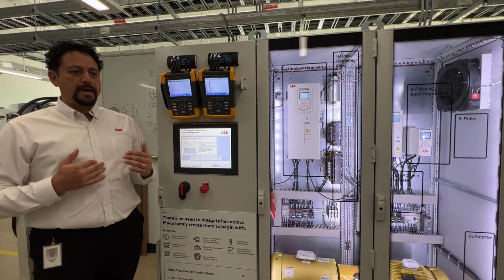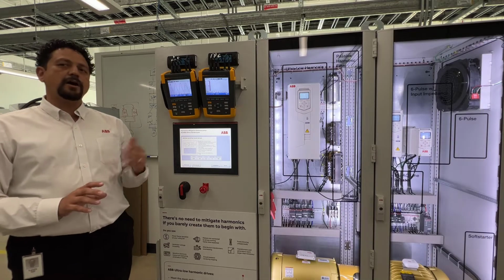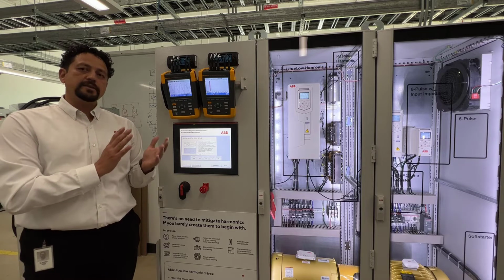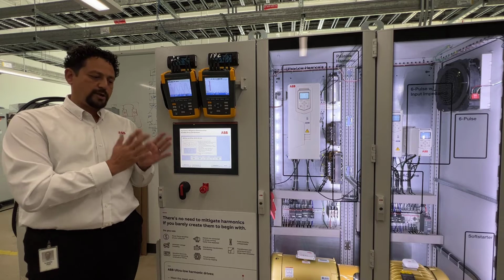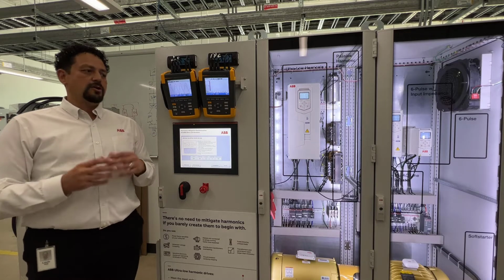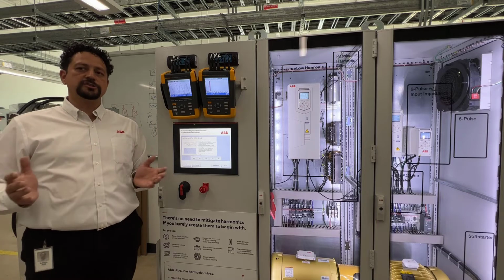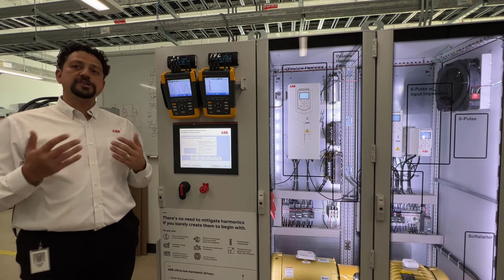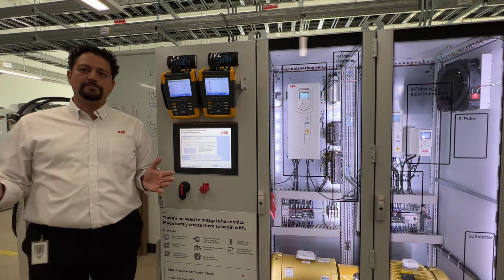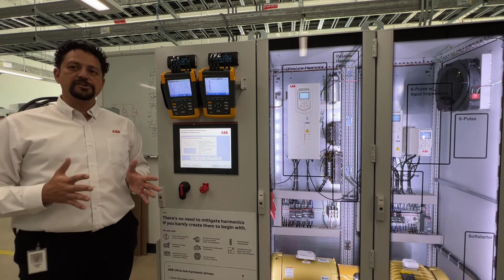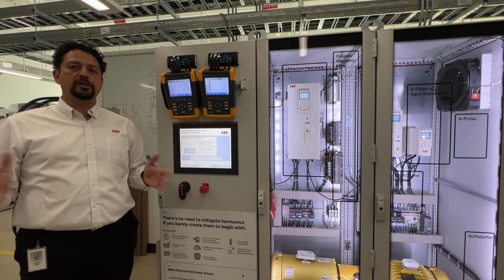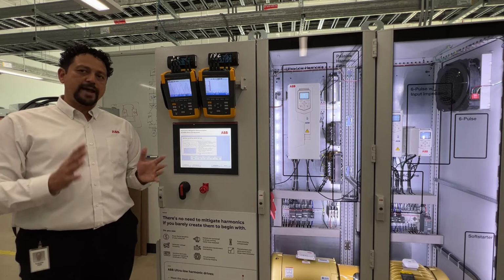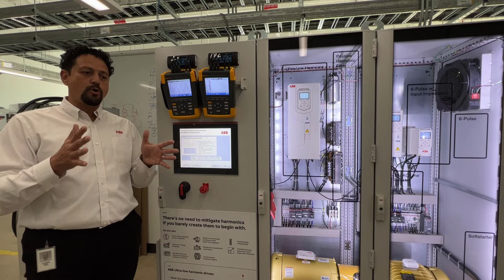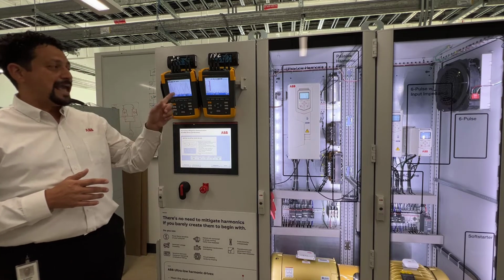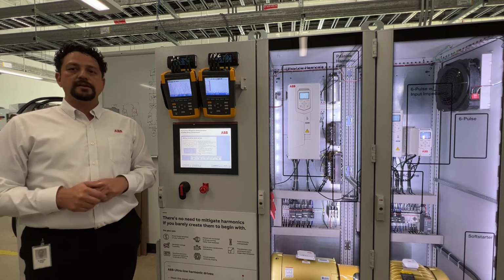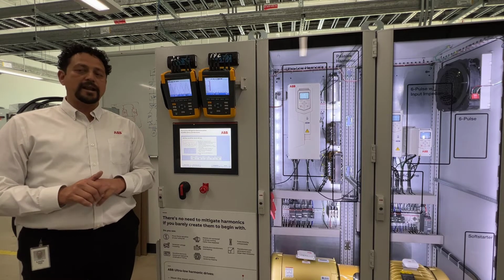One of the benefits of the ultra-low harmonic drive is the power factor, right? With unity power factor, you're using the power most efficiently. You're not creating waste where you get heat off of cables or excess heat off of transformers and distribution systems. It also helps in reducing risk in your electrical system. Imagine you have a backup generator. If you size it for 6 pulse drives, you'd have to way oversize it to handle all the harmonic distortion. But with the ULH package, you might be able to size it more appropriately for the application because you're not creating the harmonic current at all. These are some things you should consider when looking at harmonic mitigation in your facility.